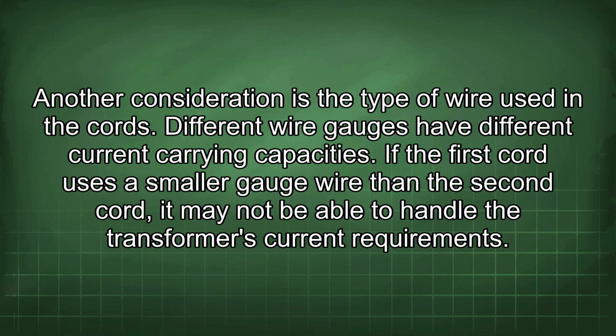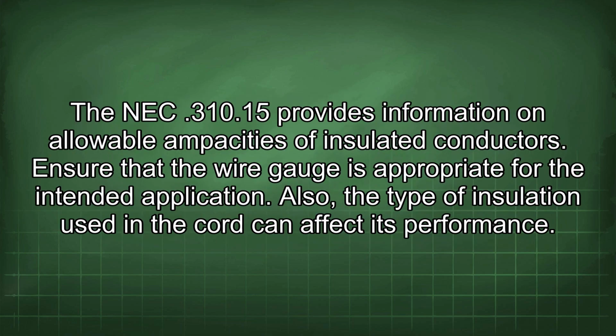Another consideration is the type of wire used in the cords. Different wire gauges have different current carrying capacities. If the first cord uses a smaller gauge wire than the second cord, it may not be able to handle the transformer's current requirements. The NEC 310.15 provides information on allowable ampacities of insulated conductors. Ensure that the wire gauge is appropriate for the intended application.